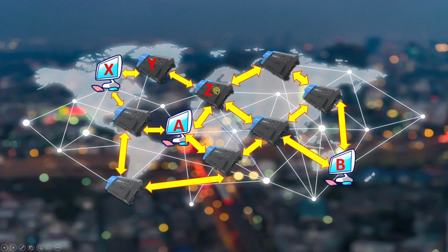While copying the station, you have to put in the Y passphrase, not the X you originally created it with, because you took the backup from the Y JACE. Likewise, if you take a backup from Z and bring it back to a supervisor with A, you're not going to use A, you're going to use Z, not Y. So the chain follows. Wherever you take the backup, the station backup holds the passphrase of the host machine you took the backup from.